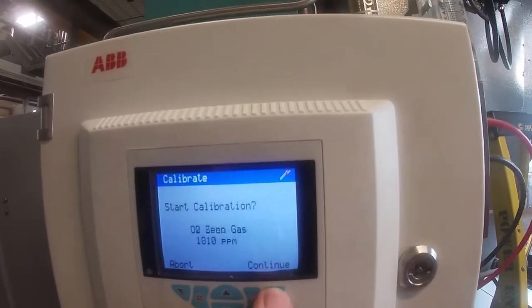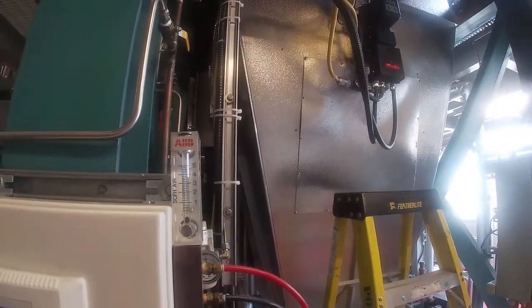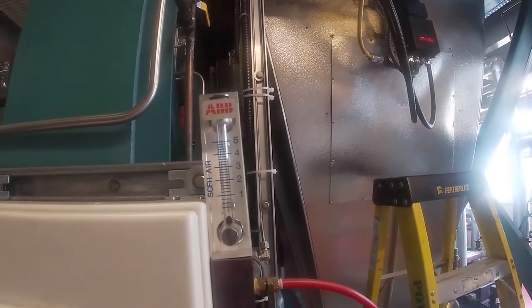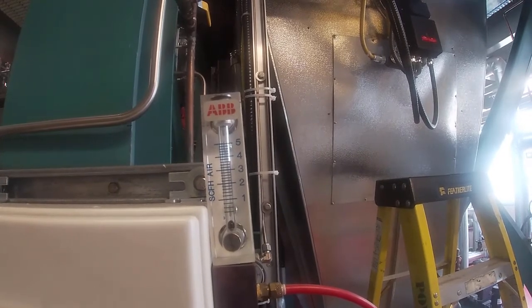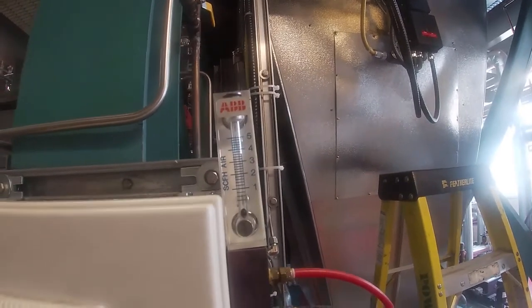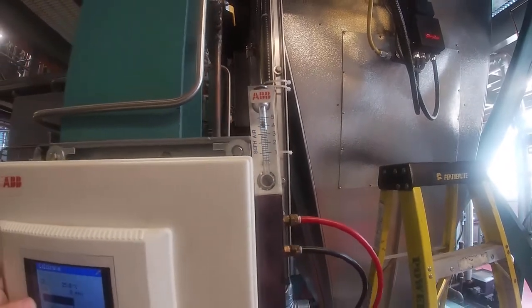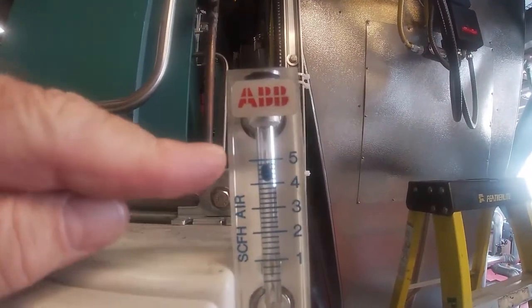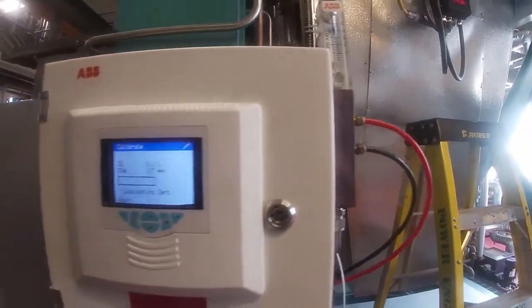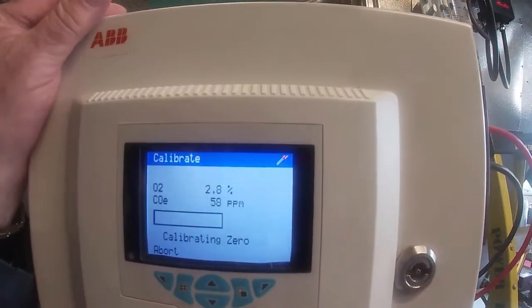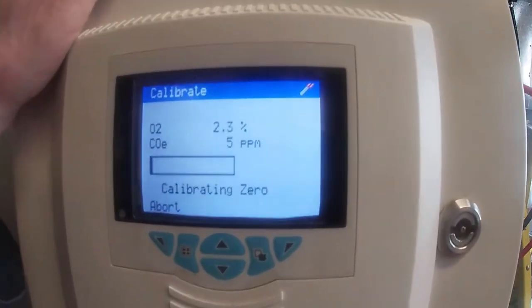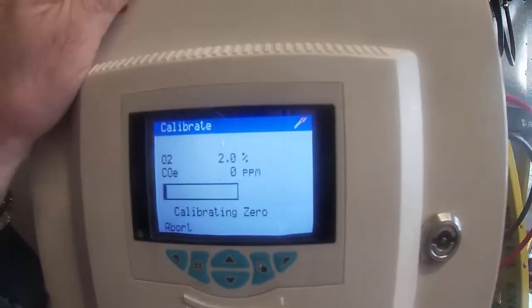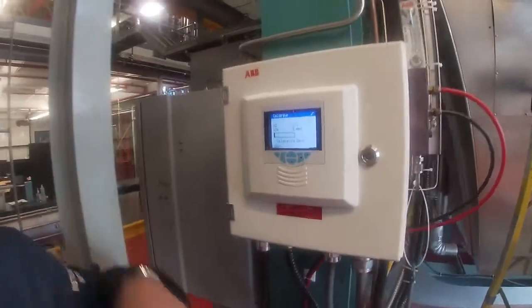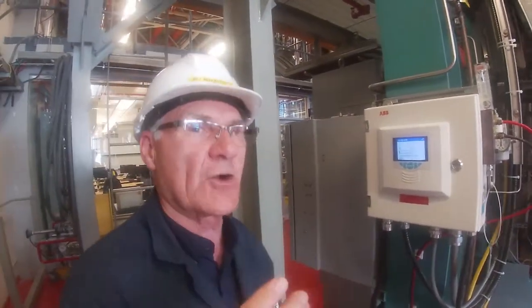So now I'm going to hit the continue button. As soon as I do, the blowback is going to happen again for a couple of seconds. 1, 2, 3. And then as soon as I get to the end of this, it should now go to calibrating 0. And my 0 gas just came up, and we are now injecting the 0 gas. And this is what the sensor is actually seeing. It's seeing 2.3% O2 and 5 ppm CO. It's sort of telling you what it's seeing as it's measuring this gas. Now this is going to go on for 5 minutes, so we'll cut this.